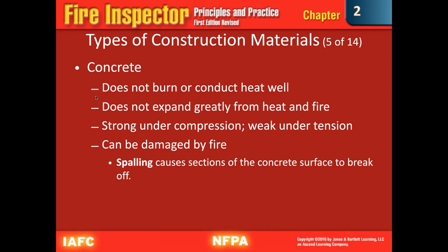Concrete, this is also naturally fire resistive. This doesn't burn or conduct heat very well. It's often used to insulate other building materials. So when we talk about type 1 and type 2 construction, type 1 being protected steel, that's usually protected with concrete. Does not have a high degree of thermal expansion. It does not lose strength when exposed to high temperatures. Often used for foundations, especially out there where a lot of you guys are, concrete slabs, columns, floors, walls, roofs, and pavement. This is strong under compression, but weak under tension.